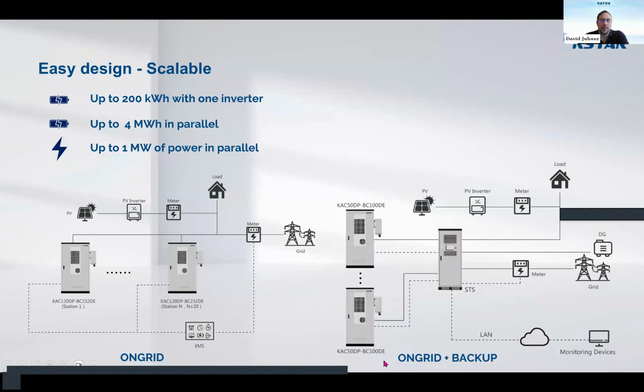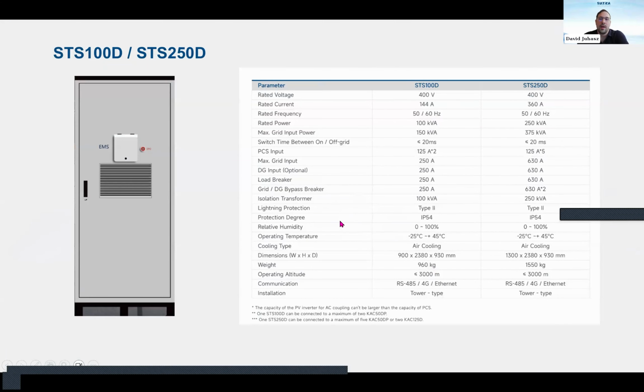If you want to use the system in on-grid and off-grid mode, we need to connect an STS to the system. This STS device has its own protections inside, the load and the circuit breakers, the load breakers. To mention something, there are two types of STS. One is the 100D and one is the 250D.